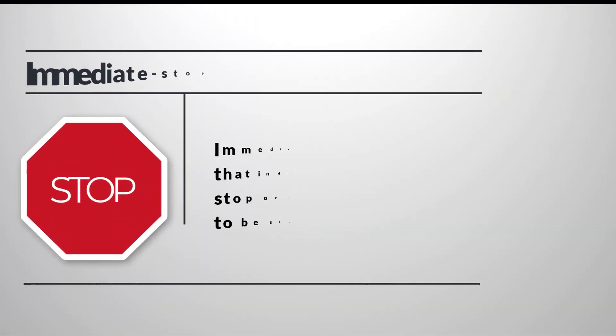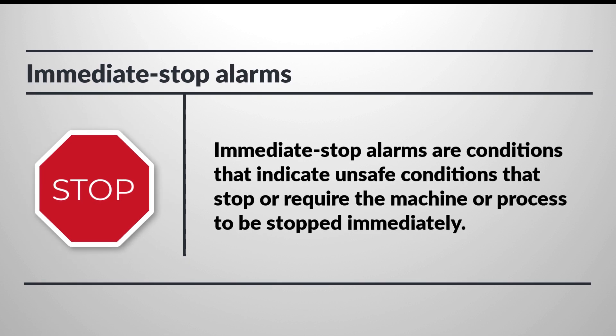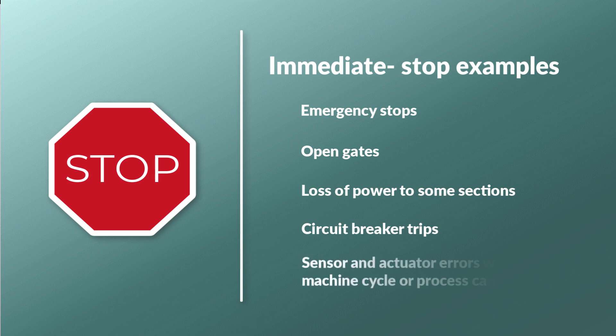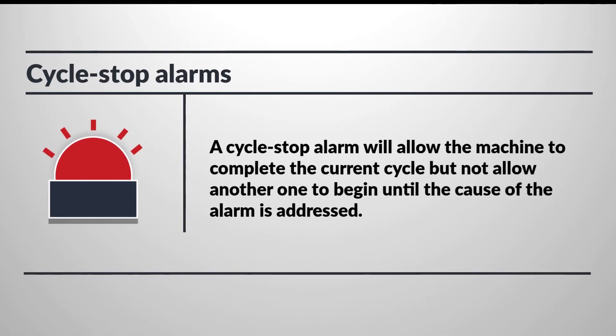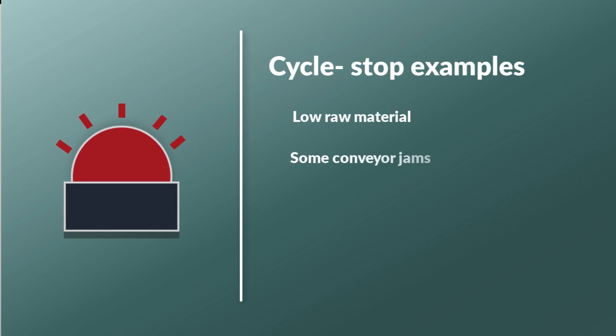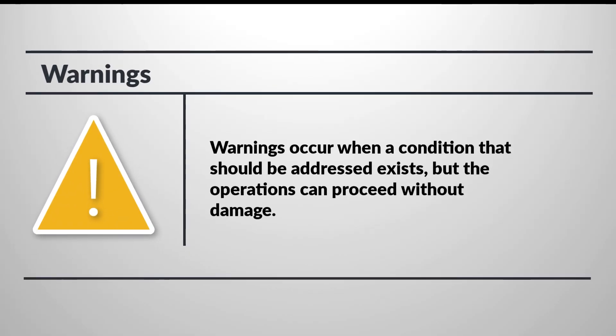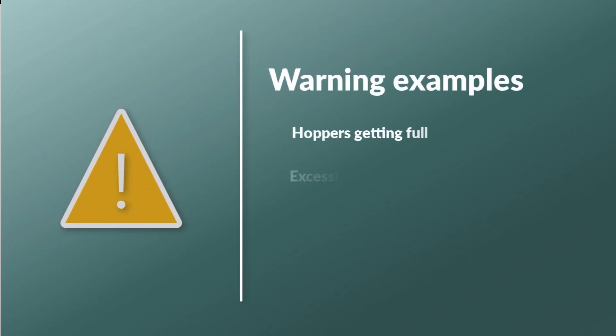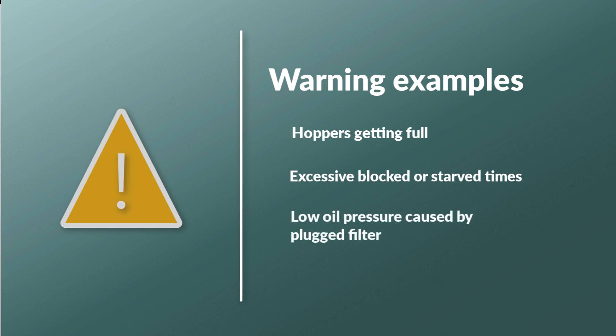Alarm indication is important in HMIs and is generally broken down into at least three categories. Immediate stop alarms indicate unsafe conditions that stop or require the machine or process to be stopped immediately. Examples include emergency stops, open gates, loss of power to some sections, circuit breaker trips, or sensor and actuator errors where the machine cycle cannot complete. A cycle stop alarm will allow the machine to complete the current cycle but not allow another one to begin until the cause is addressed — examples include low raw material, some conveyor jams, motors starting to overheat, or specific operations taking slightly longer than expected. Warnings occur when a condition that should be addressed exists but operations can proceed without damage — hoppers getting full, excessive blocked or starved times, or low oil pressures caused by plugged filters are examples.